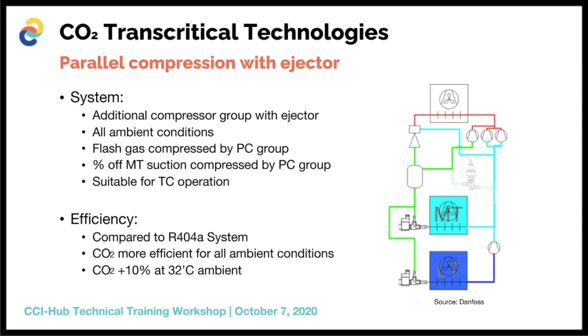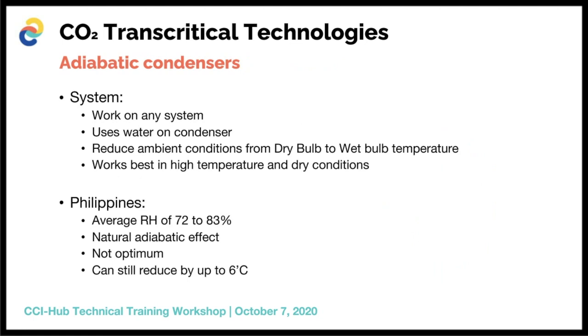Additional to the above mentioned technologies, these systems can also be equipped with adiabatic condensers or evaporative condensers. Adiabatic condensers just have the benefit of needing less water to do the work. So basically what an adiabatic condenser does for you, it reduces your dry bulb ambient temperature down to a wet bulb temperature, your wet bulb temperature always being lower than your ambient conditions. So basically you are manipulating the ambient conditions to be at a lower condition temperature, and that obviously then reduces the operation of your system and leads to energy efficiency.